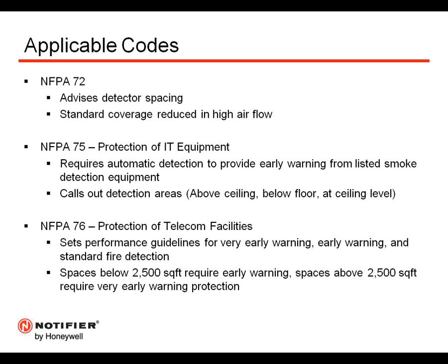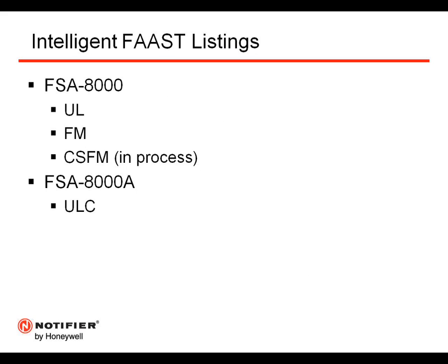NFPA 76 sets the guidelines for very early warning and standard fire detection. Very early warning detection says that transport time from the farthest hole in the aspirating pipe network can be no longer than 60 seconds. Sample port spacing has to be 200 square feet, and there's a 0.2% pre-alarm obscuration level at each sampling point and 1% obscuration level for alarm. This also goes to say that spaces 2,500 square feet and below require early warning detection, whereas any space above that square footage will require very early warning fire protection. Intelligent FAAST is UL and FM approved, and we are in the process of getting CSFM approval, which we should have attained in the next week or so, and then there's also the Canadian model, which is ULC approved.